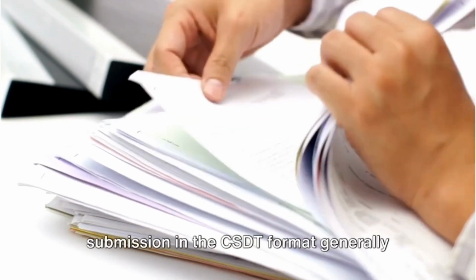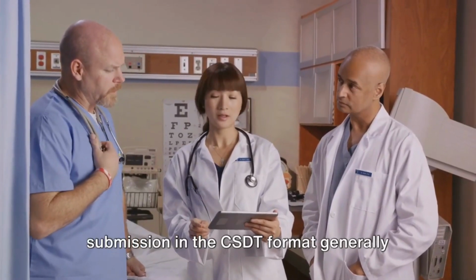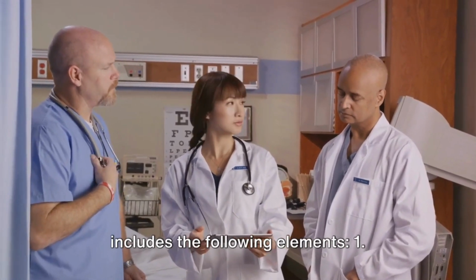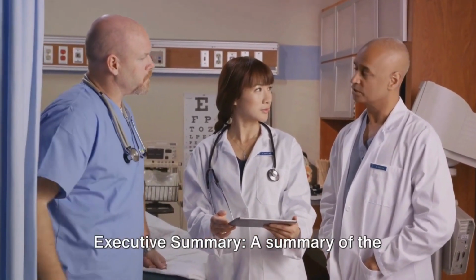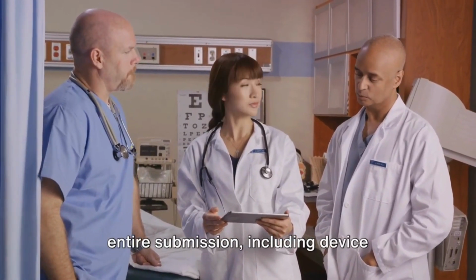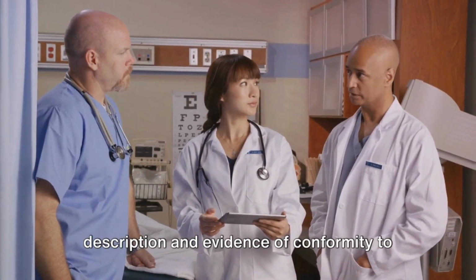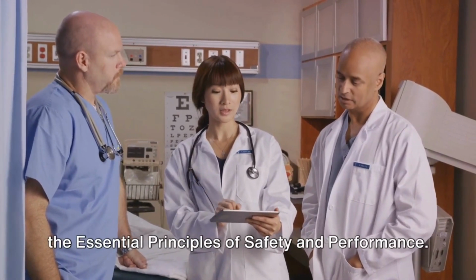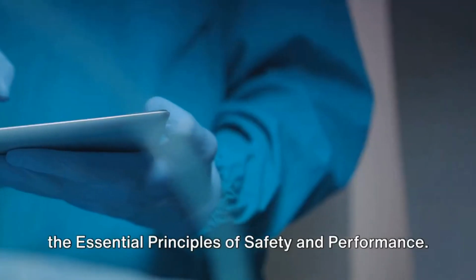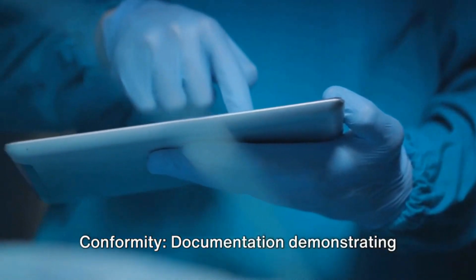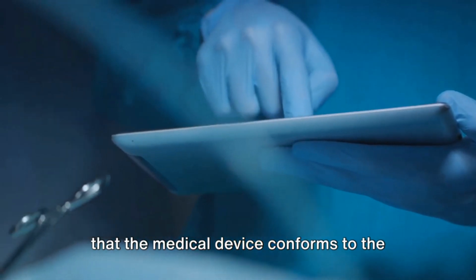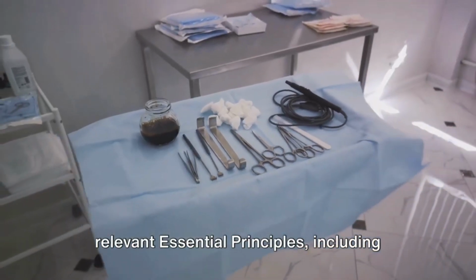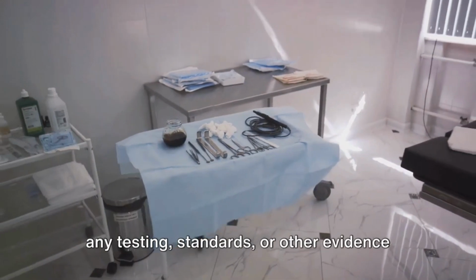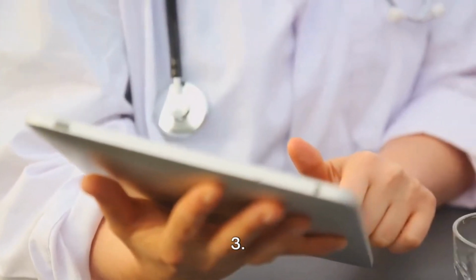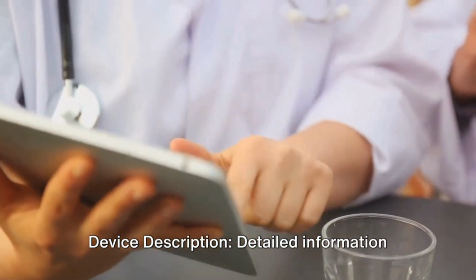The technical documentation required for submission of the CSDT generally includes the following elements. 1. Executive summary. A summary of the entire submission including device description and evidence of conformity to the essential principles of safety and performance. 2. Essential principles and evidence of conformity. Documentation demonstrating that the medical device conforms to the relevant essential principles, including any testing, standards, or other evidence used to demonstrate conformity. 3. Device description.